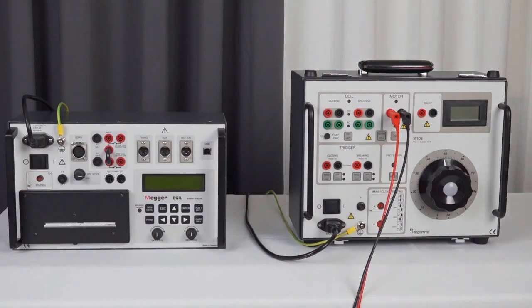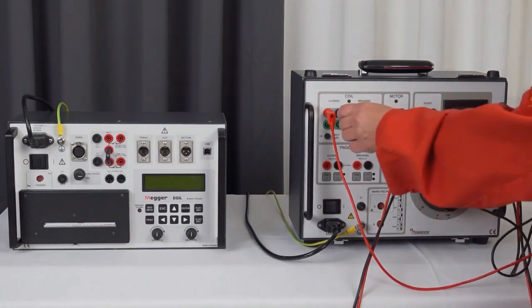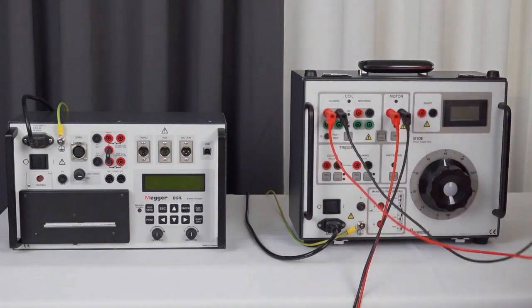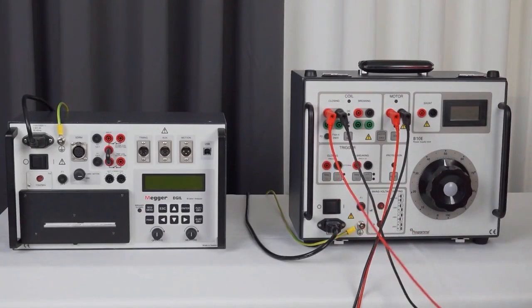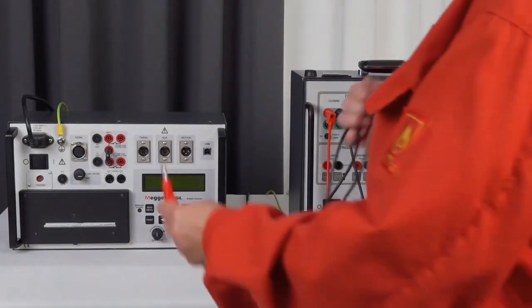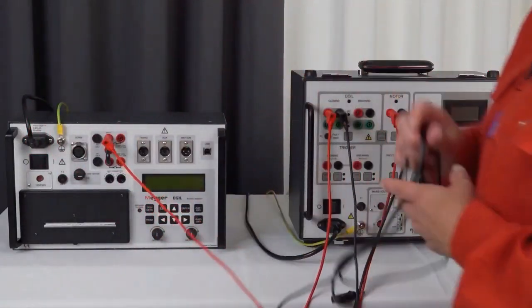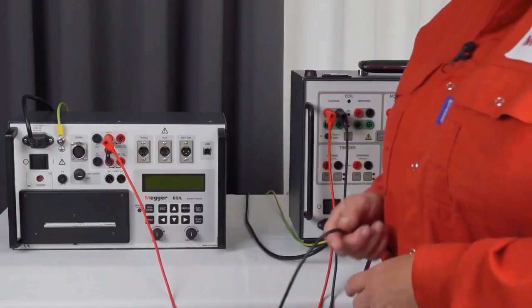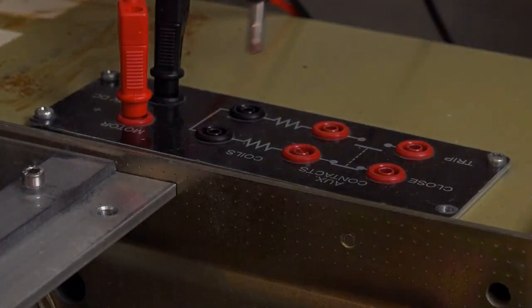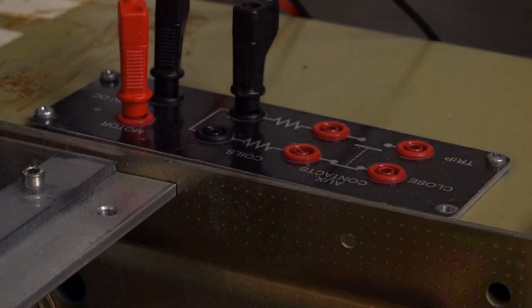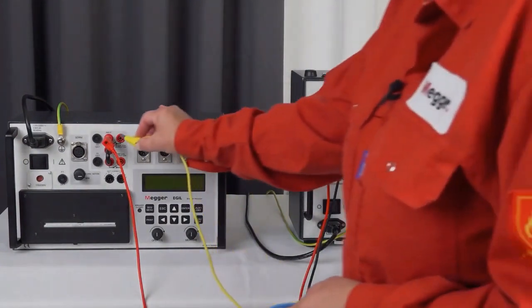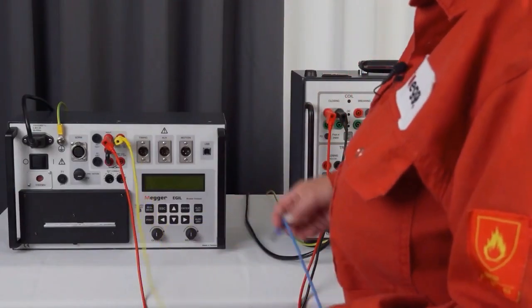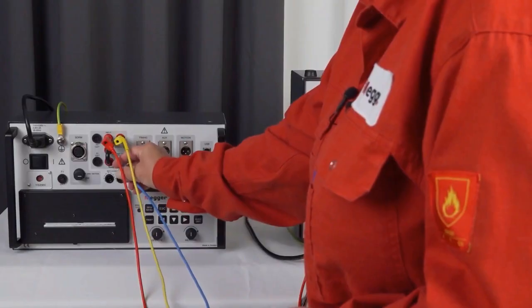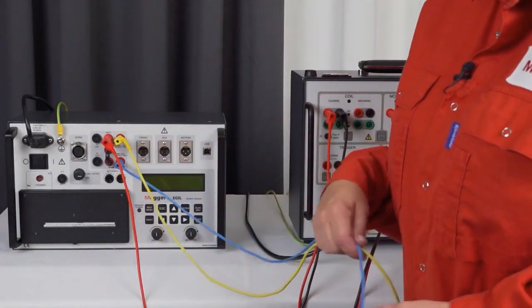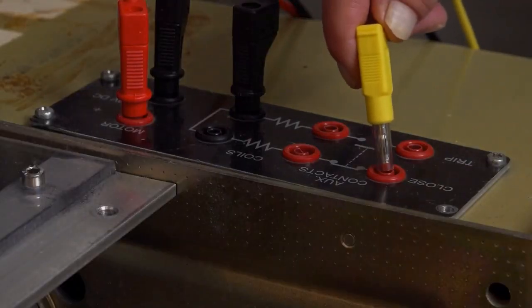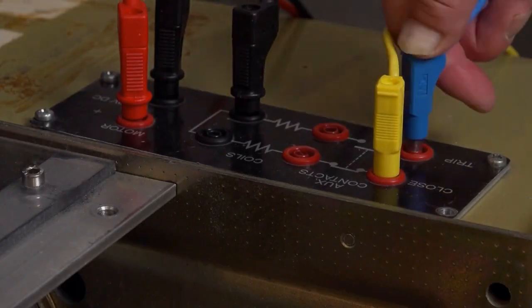I continue with connecting the coils. I need the supply, plus and minus for the coil. The plus creates the pulse, so that goes to the instrument. And we need to meet with the minus on the circuit breaker. I connect the pulses on the instrument, close, and open. And I continue on the breaker. Close and open on the breaker.